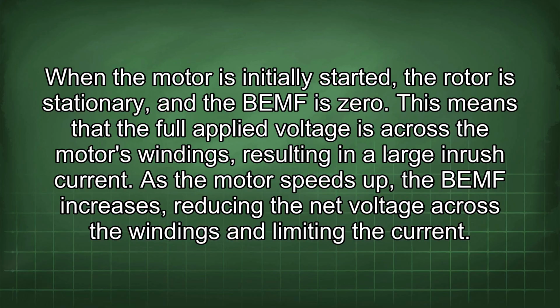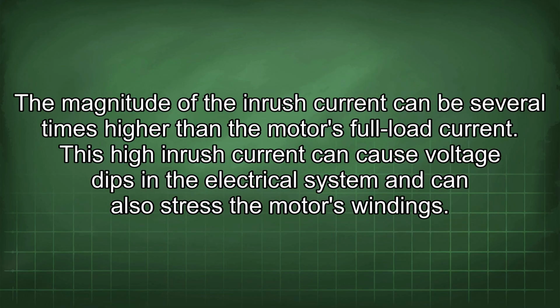When the motor is initially started, the rotor is stationary and the BEMF is zero. This means that the full applied voltage is across the motor's windings, resulting in a large inrush current. As the motor speeds up, the BEMF increases, reducing the net voltage across the windings and limiting the current. The magnitude of the inrush current can be several times higher than the motor's full load current.